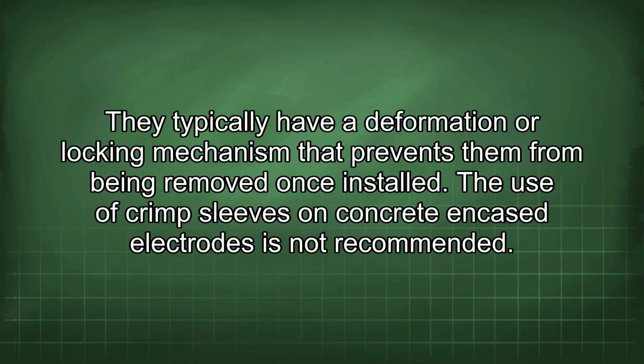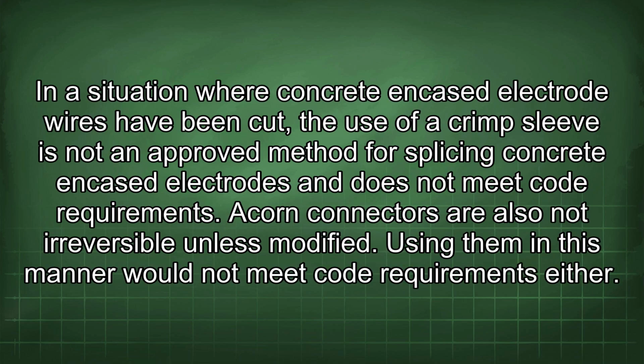The use of crimp sleeves on concrete encased electrodes is not recommended. In a situation where concrete encased electrode wires have been cut, the use of a crimp sleeve is not an approved method for splicing concrete encased electrodes and does not meet code requirements. Acorn connectors are also not irreversible unless modified. Using them in this manner would not meet code requirements either.